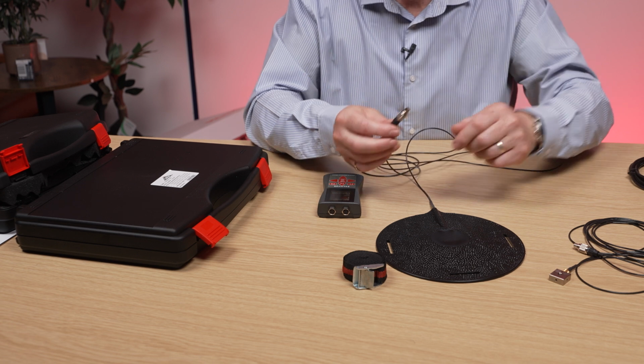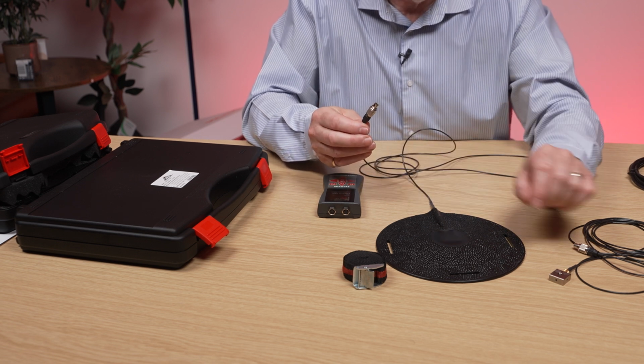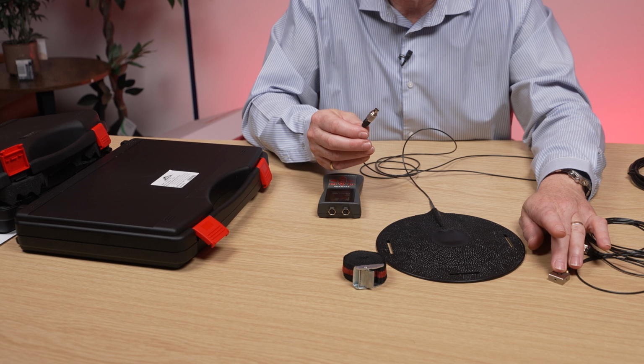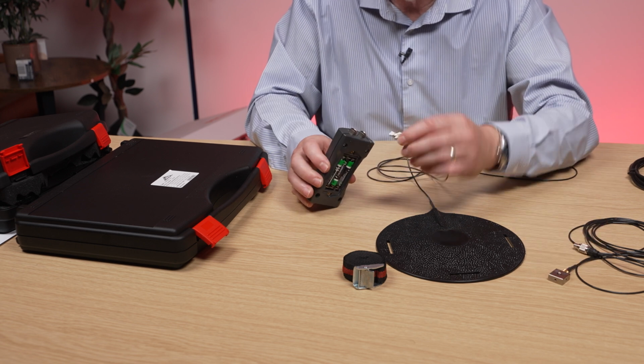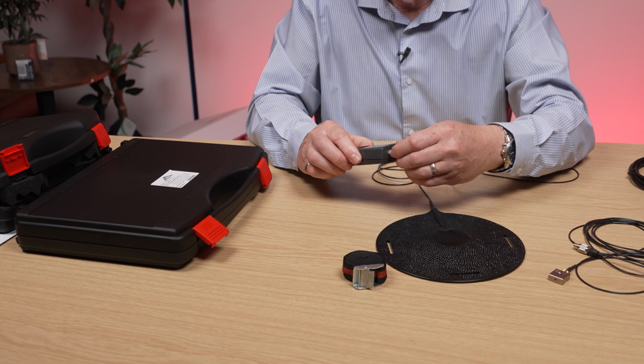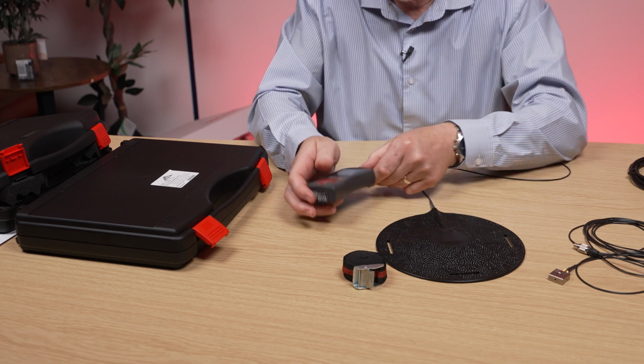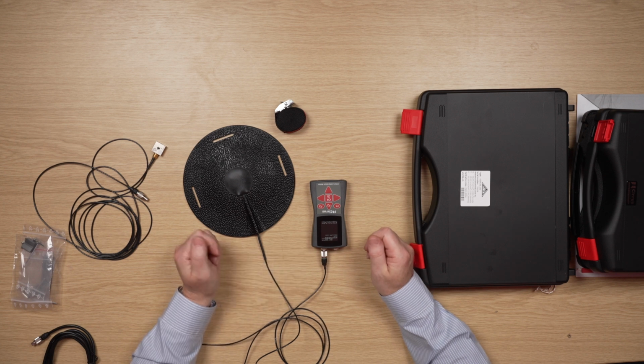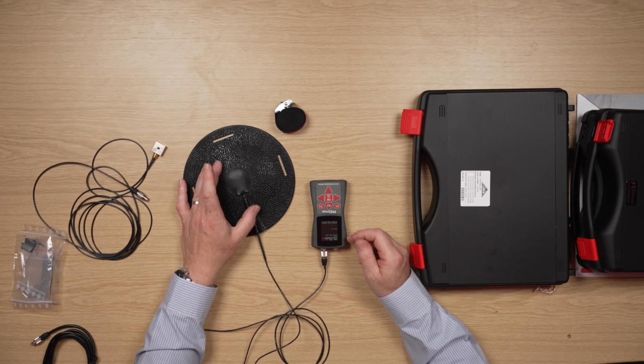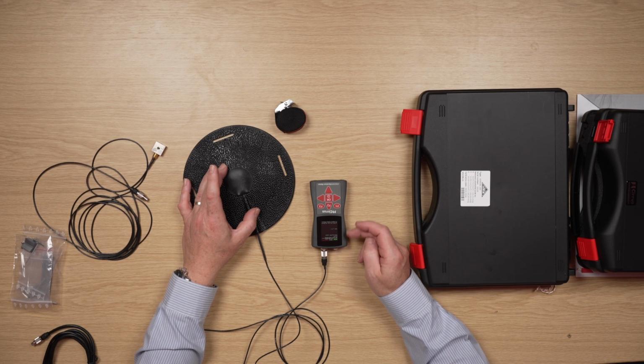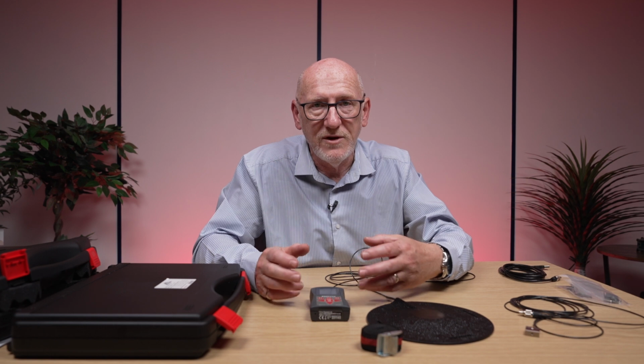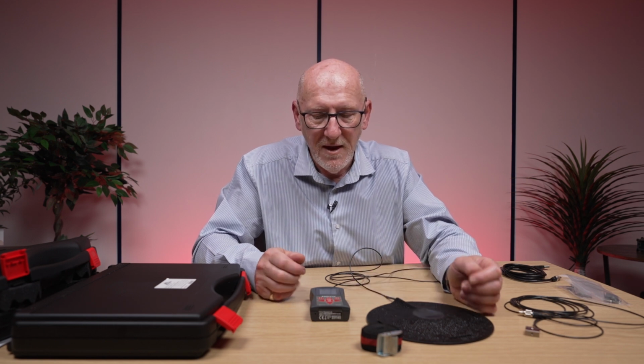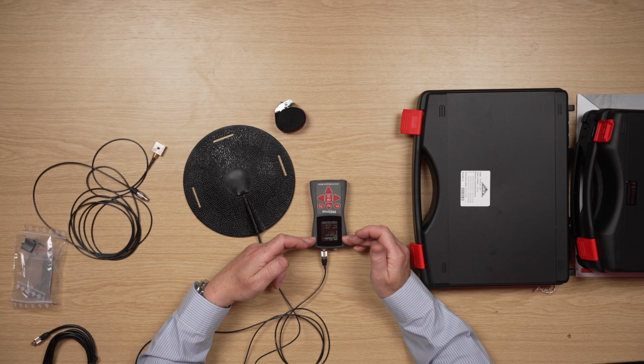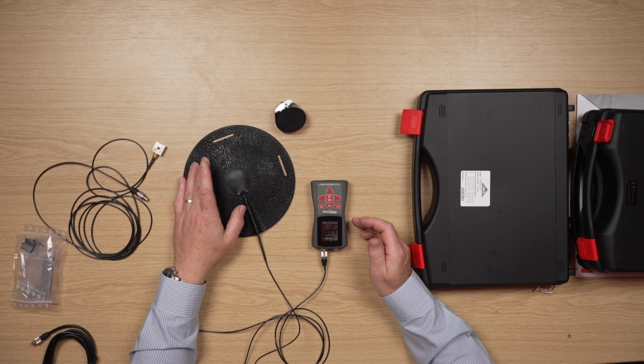So we've got a similar connector on the end of here than we had on the hand arm vibration accelerometer. And this goes in the same socket on the top of your Revo. So again, what this is going to do, it's going to basically look at the sensitivities for all three axes coming from the whole body transducer, and so it knows that it's calibrated correctly and everything's nice and accurate. So we've already preset it to whole body health, which is what we need for the whole body transducer.